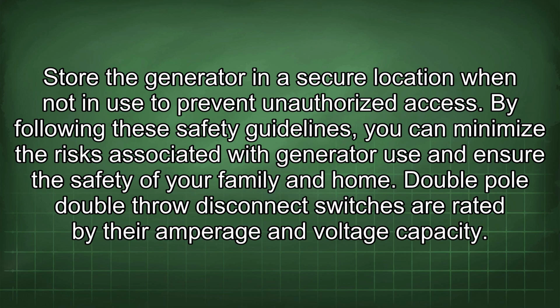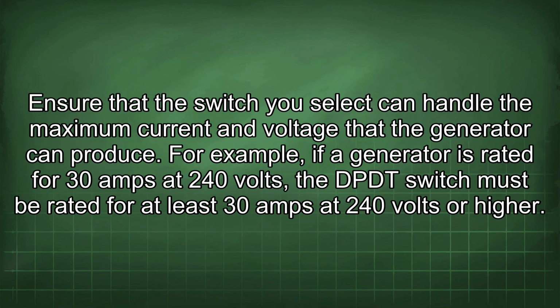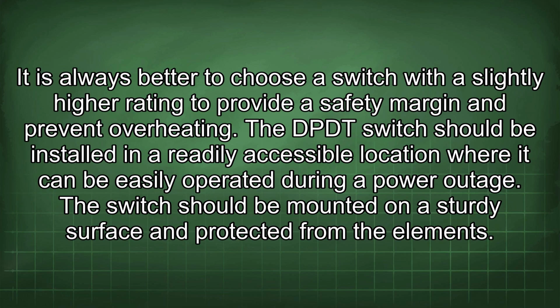Double-pole, double-throw disconnect switches are rated by their amperage and voltage capacity. Ensure that the switch you select can handle the maximum current and voltage that the generator can produce. For example, if a generator is rated for 30 amps at 240 volts, the DP-DT switch must be rated for at least 30 amps at 240 volts or higher. It is always better to choose a switch with a slightly higher rating to provide a safety margin and prevent overheating.